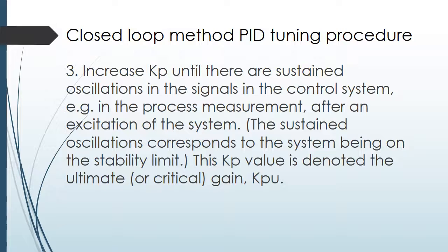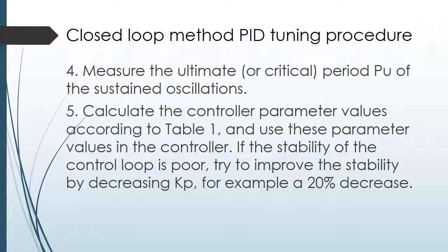For step four: measure the ultimate or critical period PU of the sustained oscillation. For step five: calculate the controller parameter values according to Table 1, and use these parameter values in the controller. If the stability of the control loop is poor, try to improve stability by decreasing KP — for example, a 20% decrease.